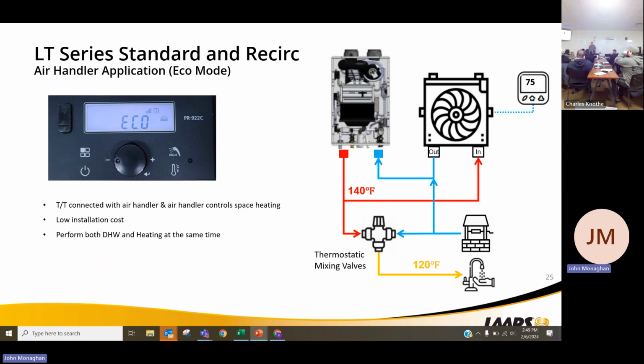You're running domestic water for a fan coil? You're allowed to do that? It's doable in some areas. I have some pieces with this, with Legionella and all of that. There's pump exercisers. There's third-party controls that'll do pump exercises. Yep. And I sort of tested it in upstate New York. I'm not worried about that. Like you said, Legionella, bacteria. Yeah, that's why the pump and the fan units are going to have an internal control with the pump there, and it'll turn on and off and do its thing to keep the water circulating.